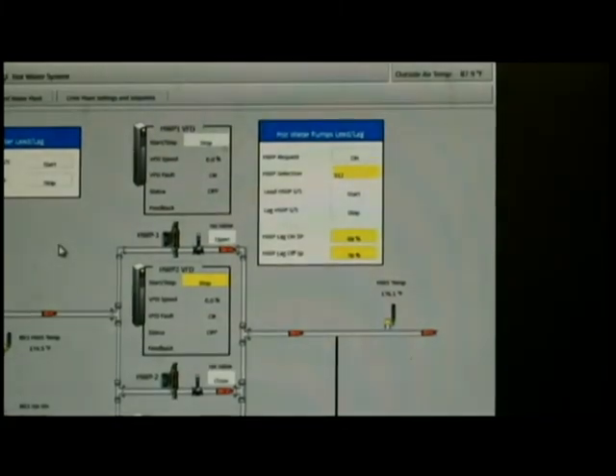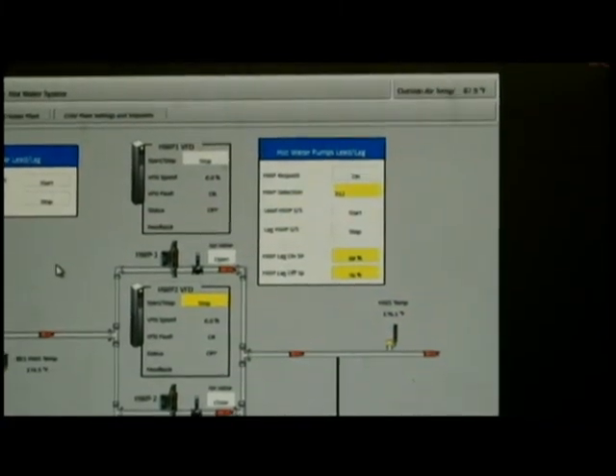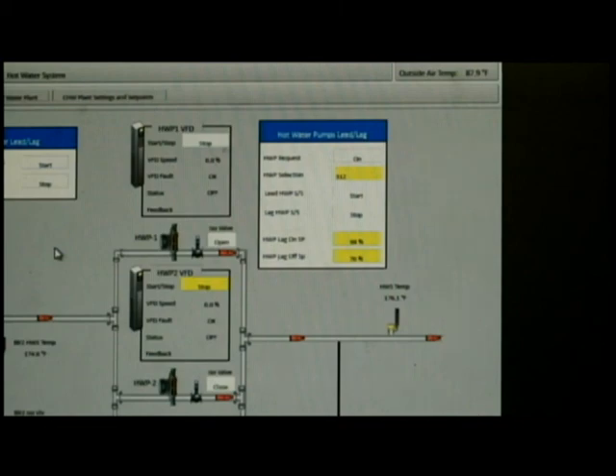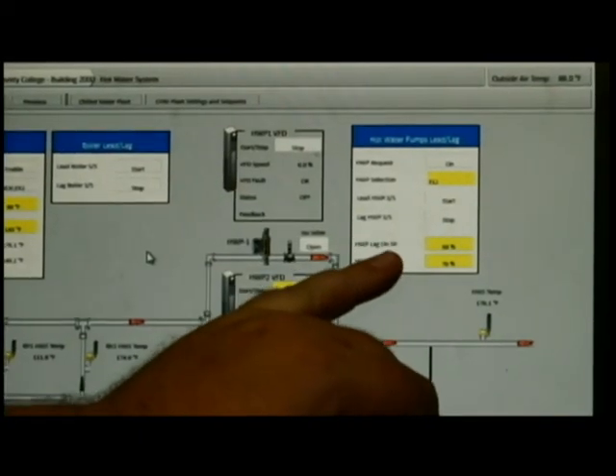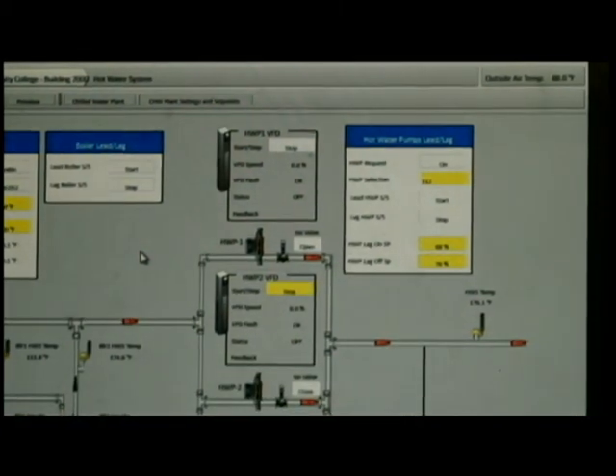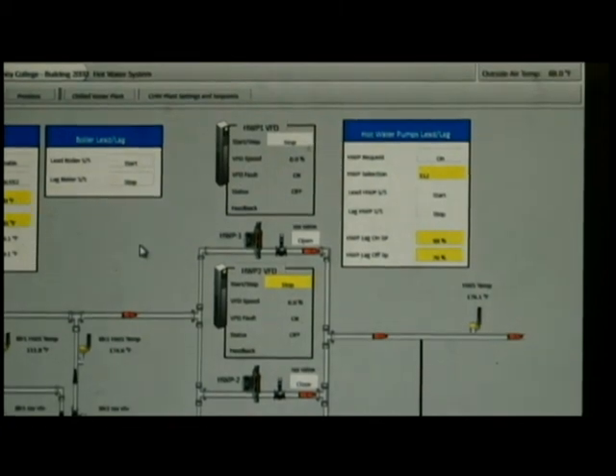Down here, just below our lead lag selection, the hot water pump selection, which chooses what order they run in, is our status flag for our lead and lag hot water pump. I don't think I've ever heard of running more than two hot water pumps at one time. So here we just have a lead hot water pump start-stop and a lag hot water pump start-stop. So for those objects, the lead, of course, is triggered by a call out in the campus for hot water, whether it's a zone or what have you. The lag hot water pump start-stop, though, is triggered by the criteria just below it. So just below it here, we have a hot water pump lag on set point and a lag off set point. So currently the lag on is 98%, the lag off is 70%.